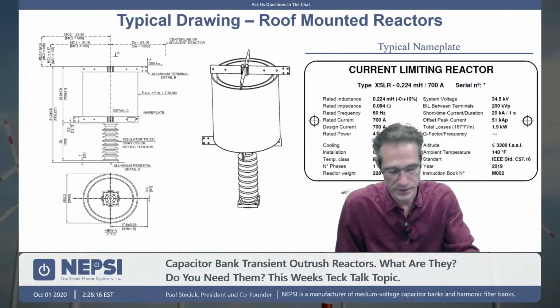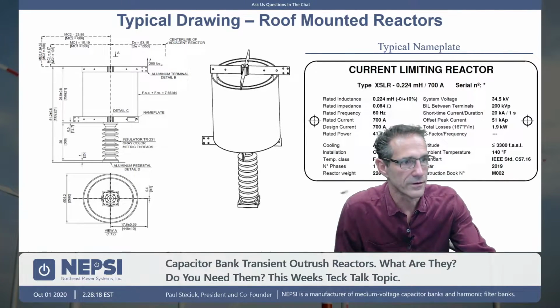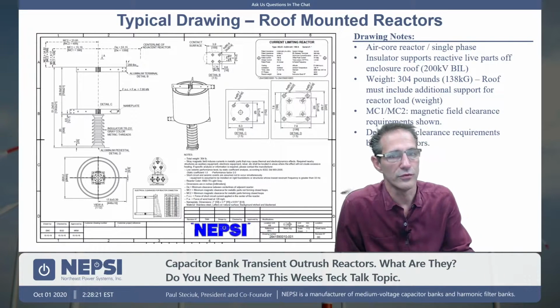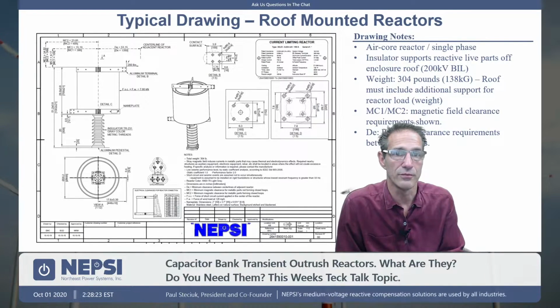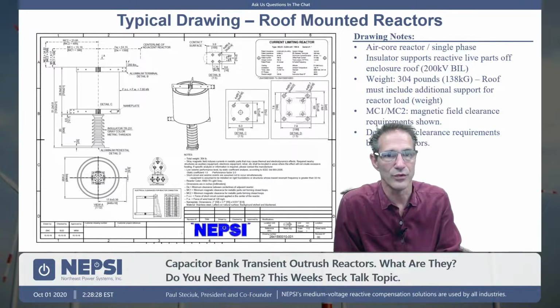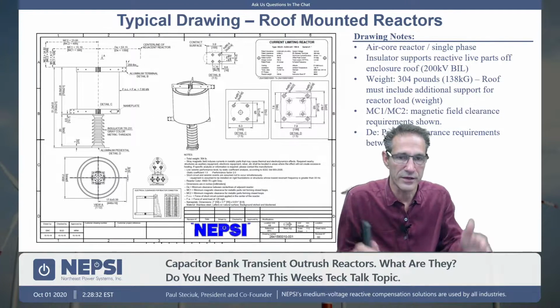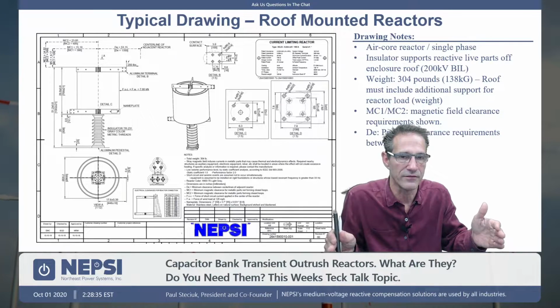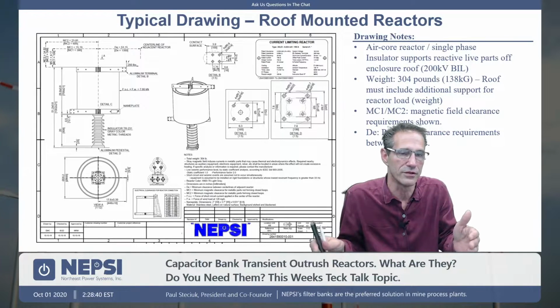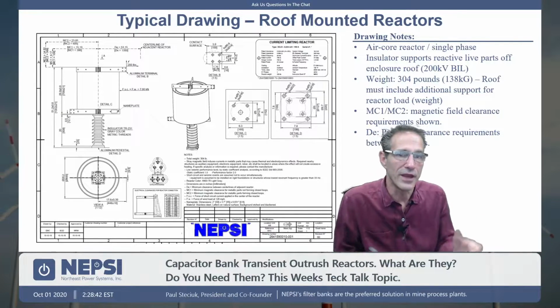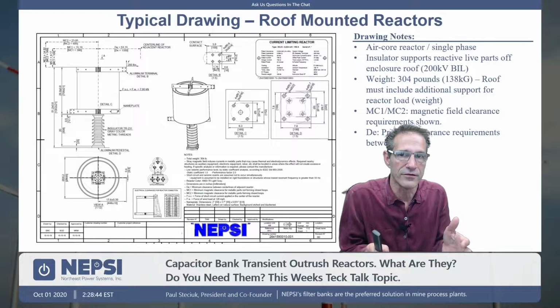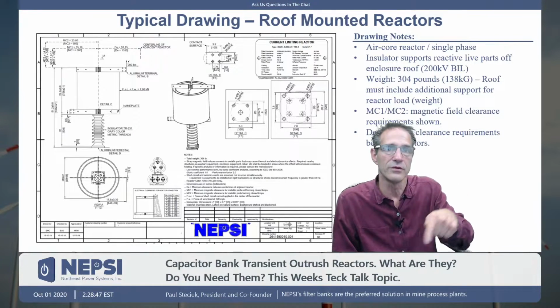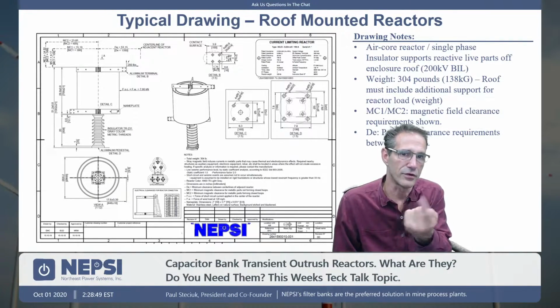So it's pretty large. And it's important to note that when you're installing these reactors, you do pay attention to the magnetic field clearance requirements, and that's the MC1 and the MC2 requirements. Basically, the reactors will have an envelope around them for which you cannot have conducting parts, either large or small. The MC1 being large, MC2 being small. If we have steel parts in that vicinity, the magnetic field flowing through the metal will create an eddy current. That eddy current causes heating.